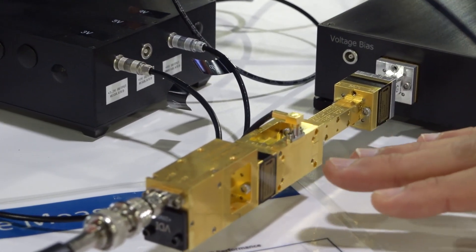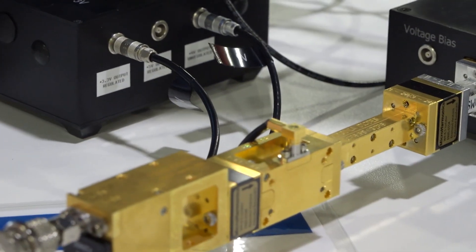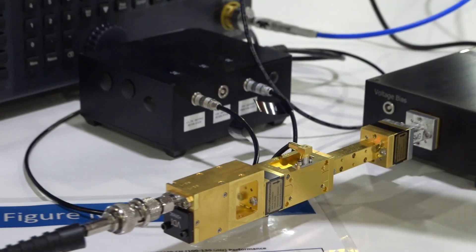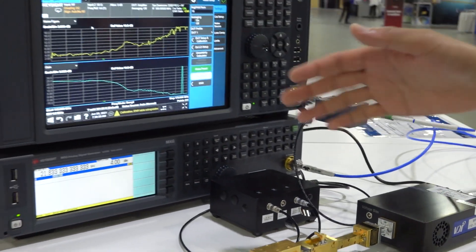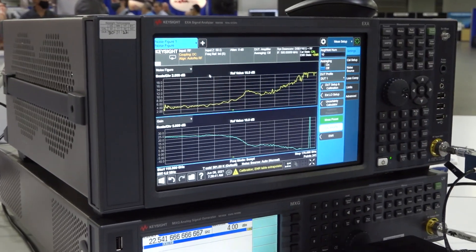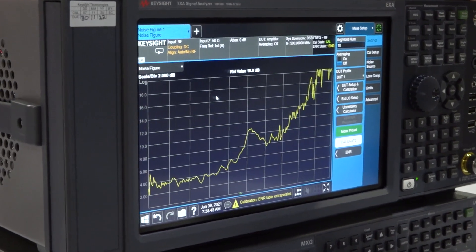You can see after you do the calibration, you place the device under test in between the noise source and the down converter. You get a gain measurement and also a noise figure measurement.